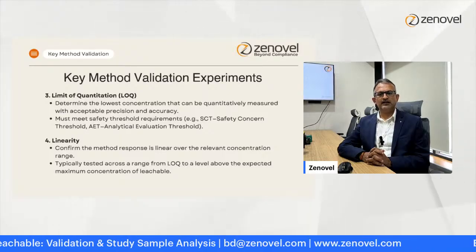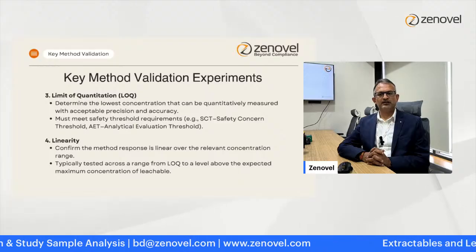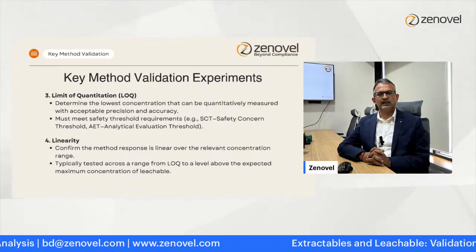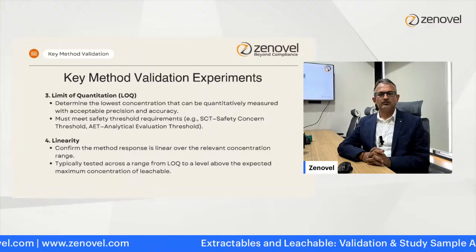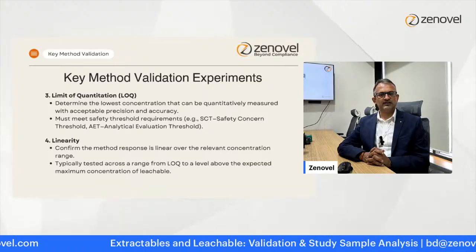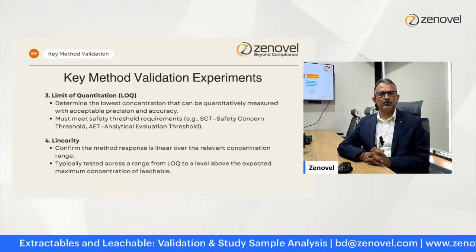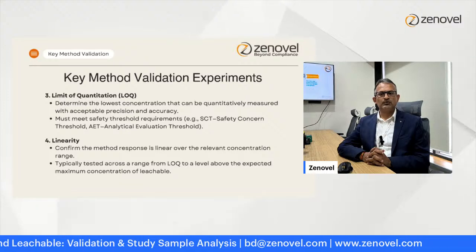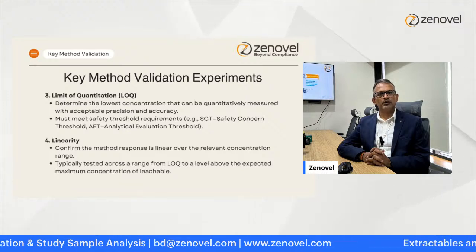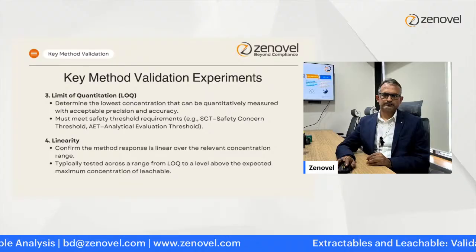The next is linearity, to confirm the method response is linear over the relevant concentration range. So typically the linearity is tested across the range from the LLOQ to the level above the expected maximum concentration of the leachable.